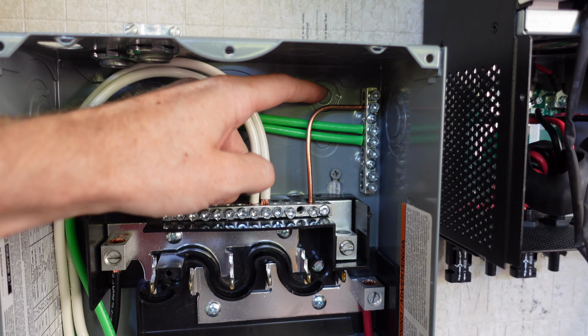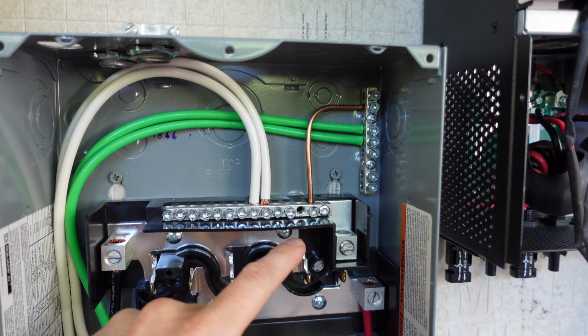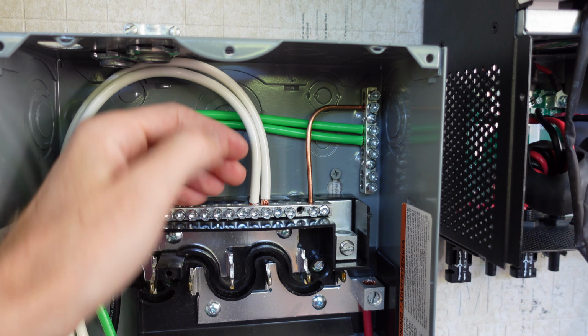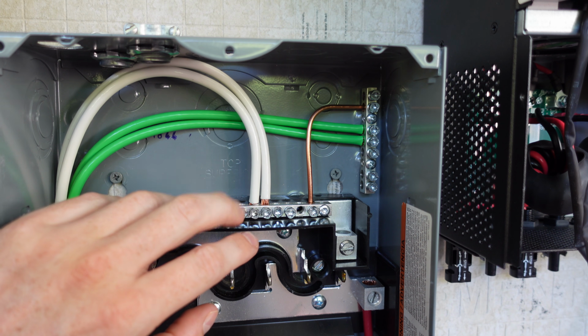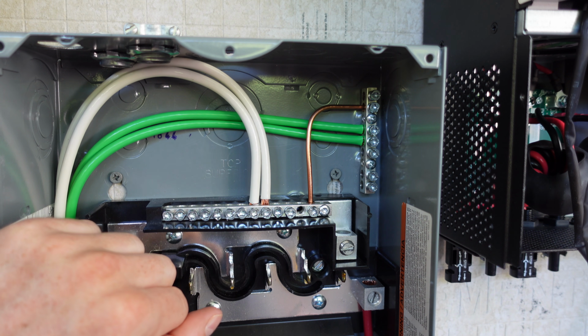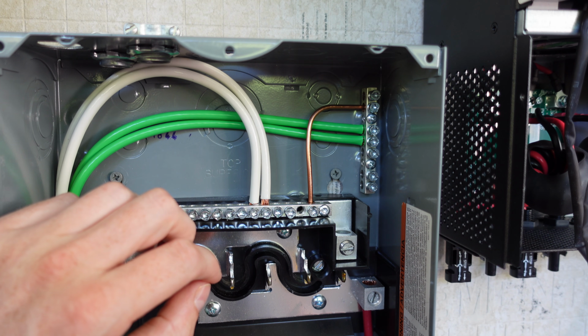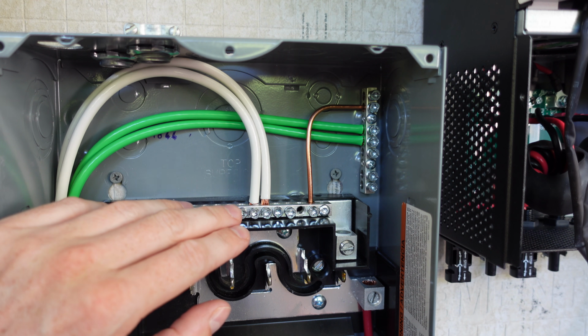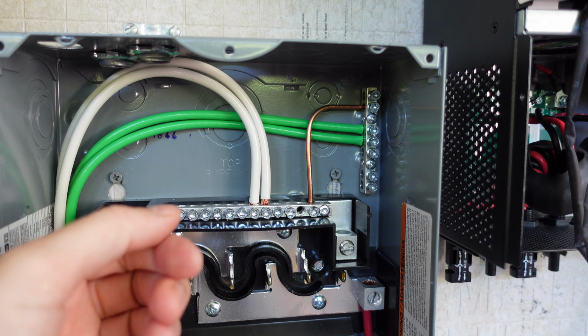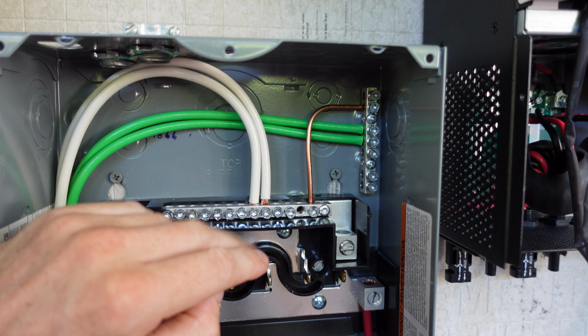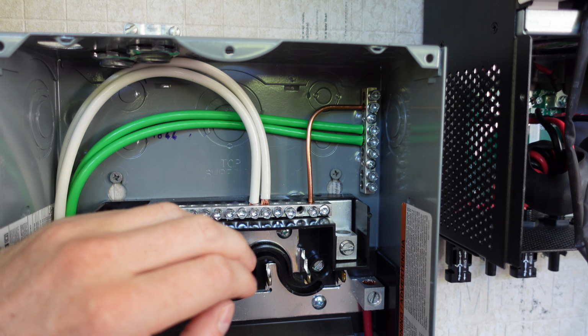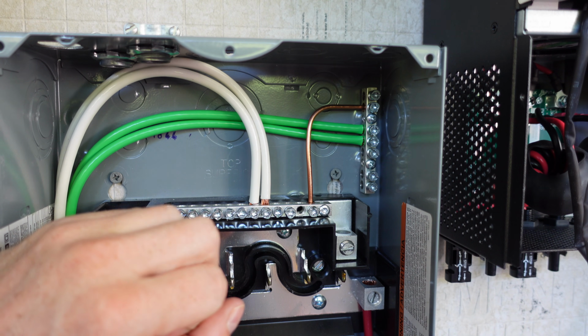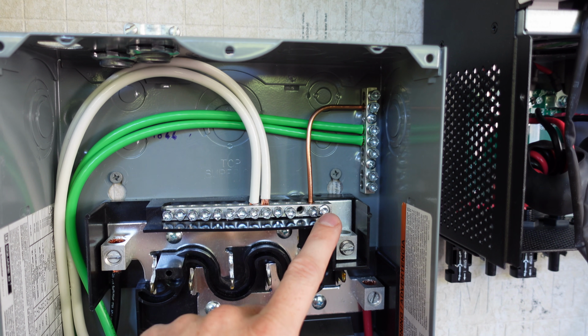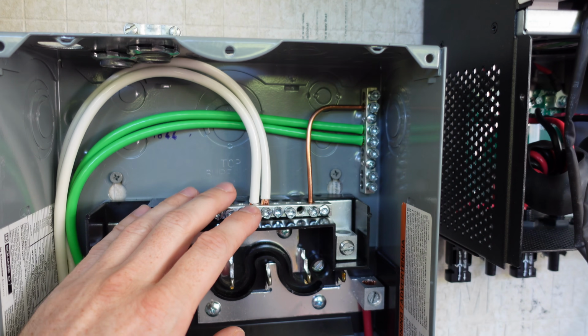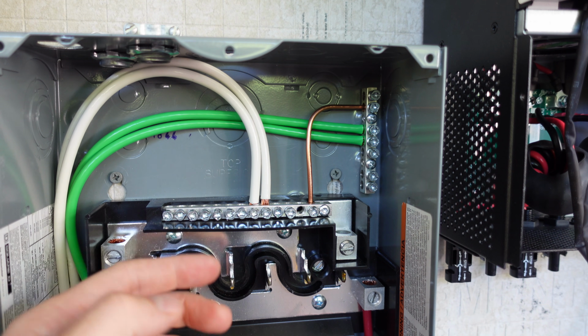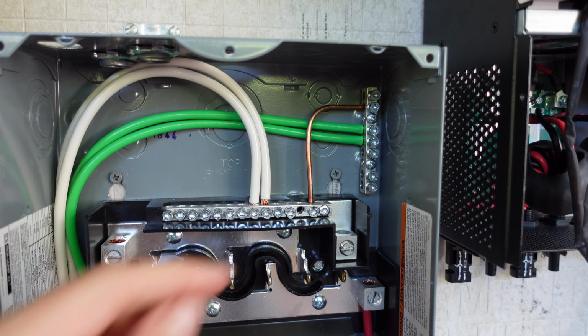Now you'll notice I have a jumper going from the ground down to the neutral bar. And this is very important because this is where my setup is probably going to differ from most other people. So by default, these inverters come with a ground neutral bond in each inverter that is engaged when the inverter is operating in off-grid mode. Per the approval of MPP Solar, I have removed that bonding screw in each of my inverters. And I've done that because I want a ground neutral bond in the panel. You can only have the ground and neutral bonded in one location in your electrical system.